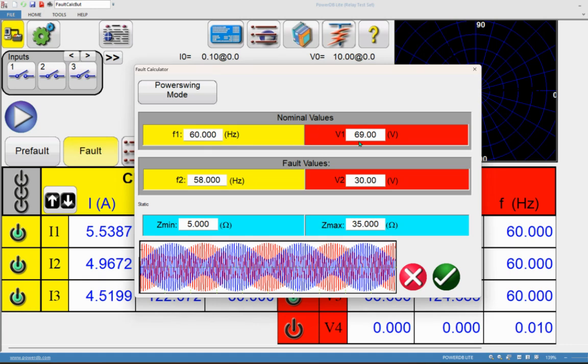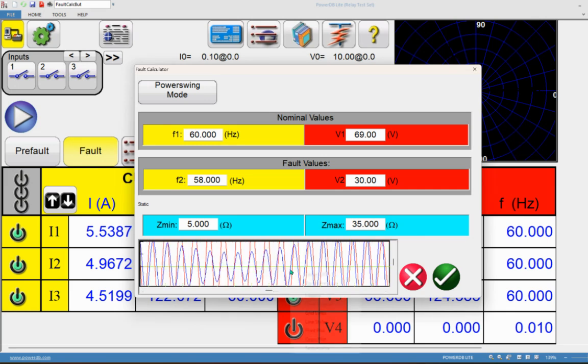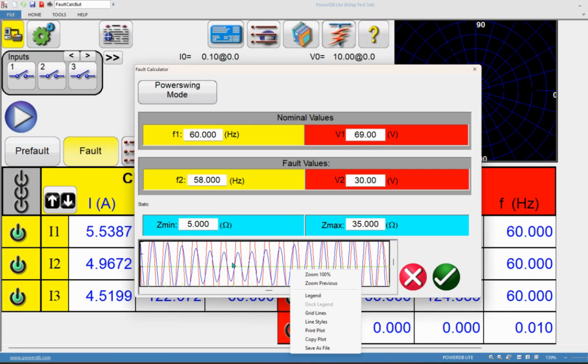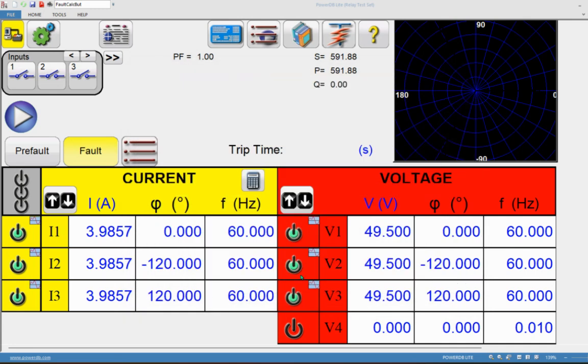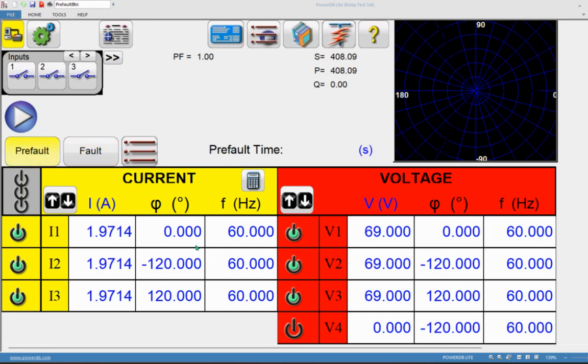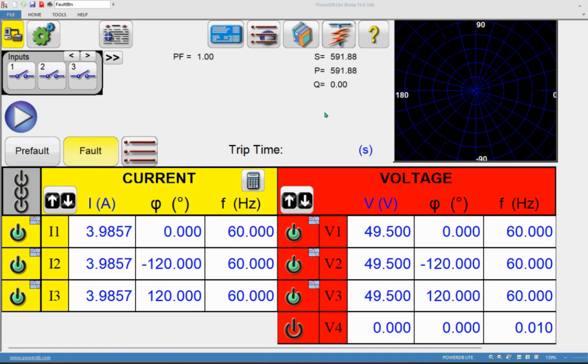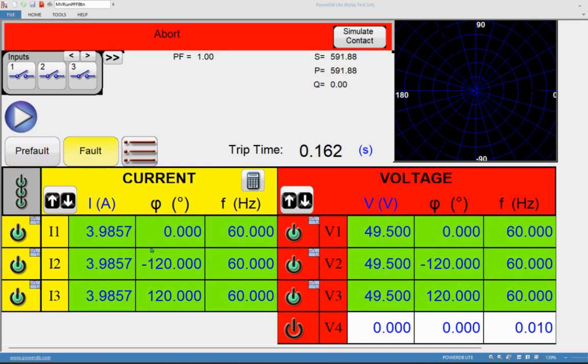Set source one frequency to 60 Hz with a source voltage of 69 volts, source two frequency to 58 Hz with a fault value of 30 volts, and define the minimum and maximum impedance of the swing condition. Click OK and the swing is automatically generated. You can zoom into the graph to see how the impedance looks. The fault calculator automatically calculates the voltage and current values for those impedance settings and also populates the pre-fault values based on the calculation.